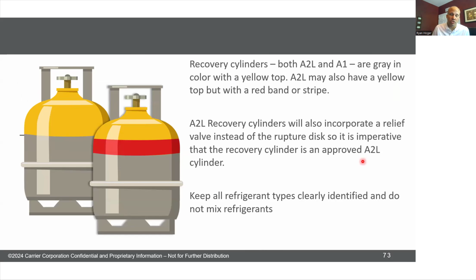Reclaimed cylinders, also left-hand threaded, also have a red band on them, also have a pressure relief valve on them. You are not allowed to put A2Ls into a standard recovery cylinder. You could, I guess, put an A1 into an A2 cylinder, but I don't know why you would do that. The cylinder costs more. So keep the A1s in here, keep the A2Ls in here. In fact, don't even mix the A2Ls.